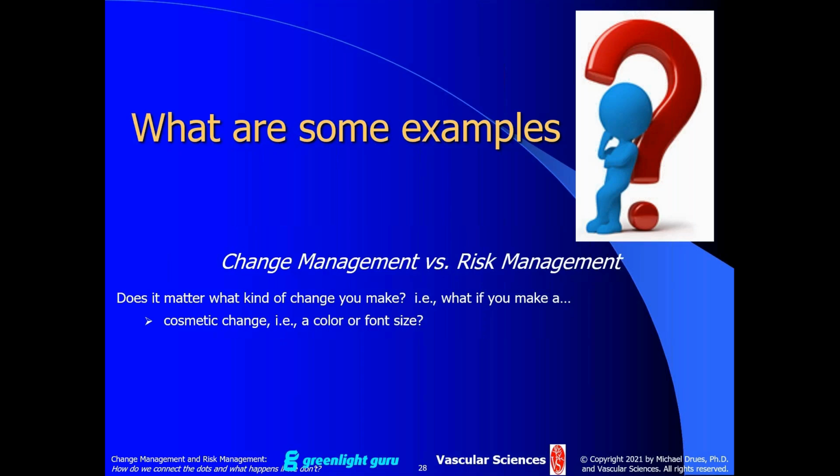It doesn't have to be a real big, formal, robust study, but just to make sure that if you change the color, if you change the font, what have you, it's not going to impact safety or performance, and especially it's not going to impact risk. We need to be able to demonstrate that some way. Whether we report that to the FDA ultimately or not, I could care less.